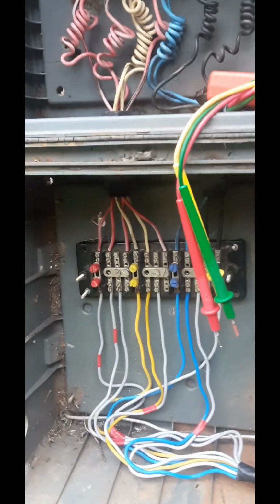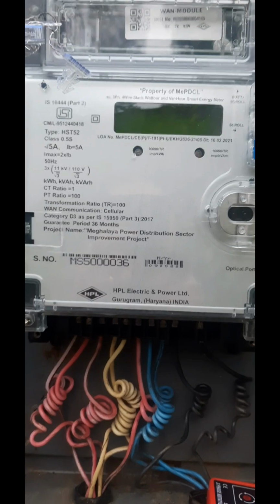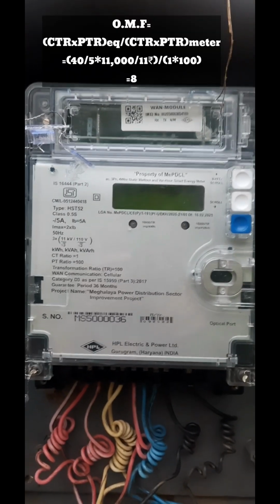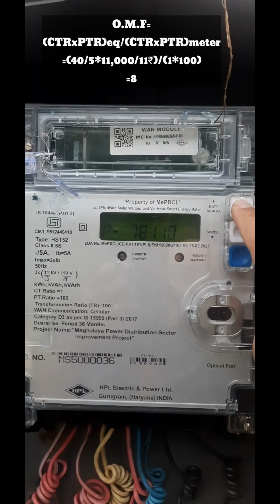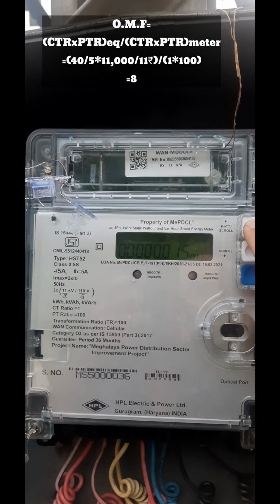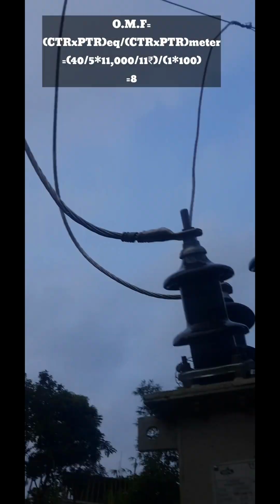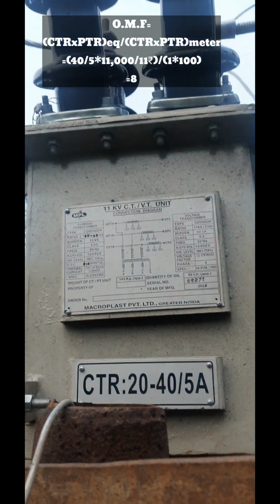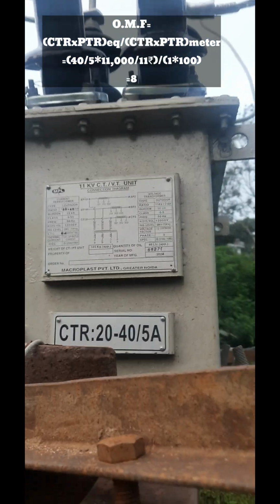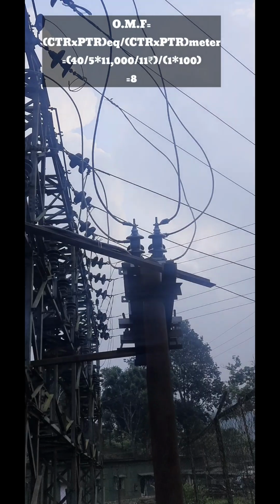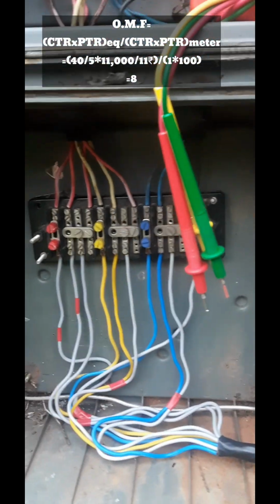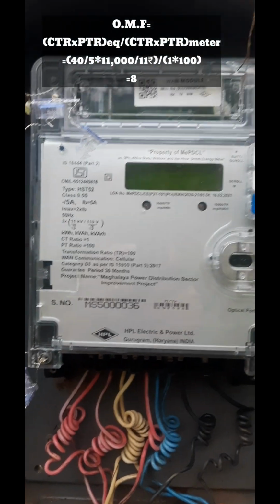OMF is equal to the CTPT ratio of the meter divided into the system ratio, which in this case our CT ratio we have chosen to be 40 by 5, and our PT ratio is fixed, 11 kV by 110. And that of the meter, the CT is 1 and the PT is 100. When you calculate this you will get 8. So 8 is the MF.